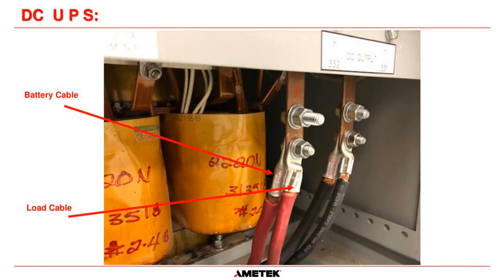So this here, this is your positive and your negative output from the charger. And what they've done is this back cable here, this is the battery cable, and this front cable here is the load cable. So you can see, say we had a problem in this charger and we wanted to keep the load circuits powered up with the battery, this one at the back here. That's going to be impossible for us because we would have to undo this bolt here to disconnect the charger. And in doing that, in loosening that bolt, we are going to make a disconnection to your load circuits, and your load circuits are going to be dropped.